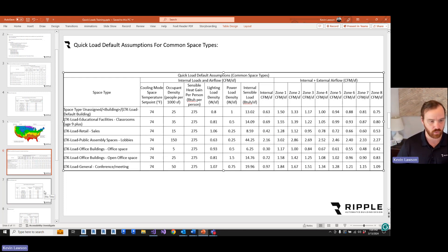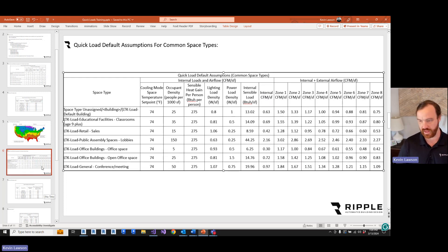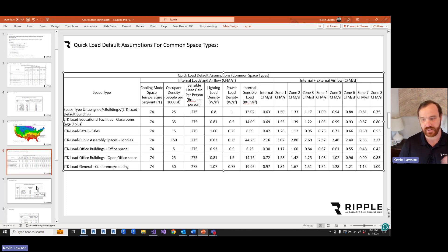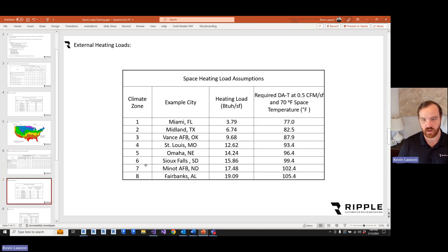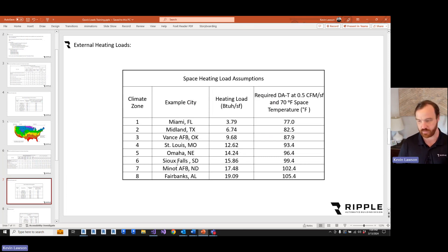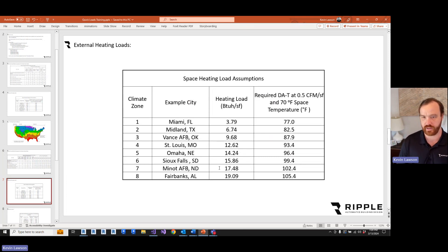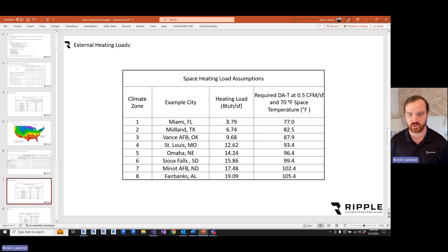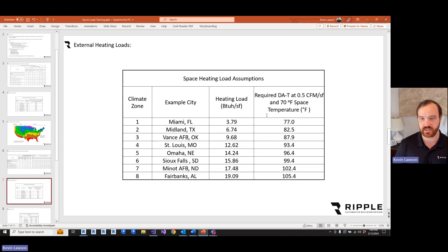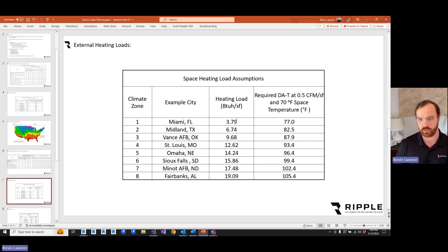Now, from that, that's for cooling load. And that's what you calculate your specified supply air CFM from. Now, for heating load, it's going to be a little bit different. There's not a lot of good rule of thumb for heating loads like cooling loads at CFM per square foot. Most engineers can think about that in their head. But for heating loads, here are the assumptions we made for BTU hours per square foot.